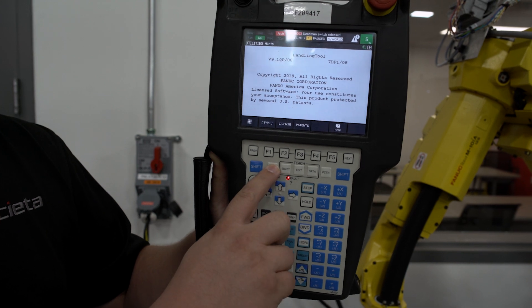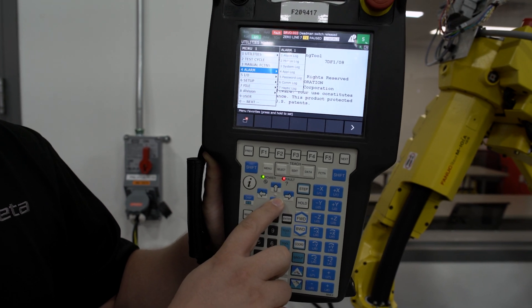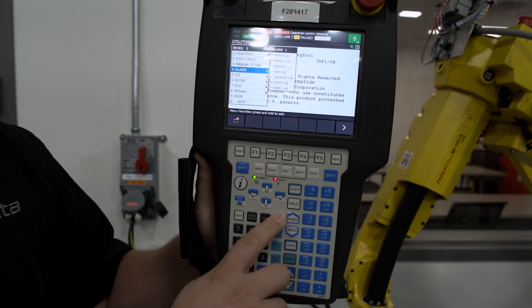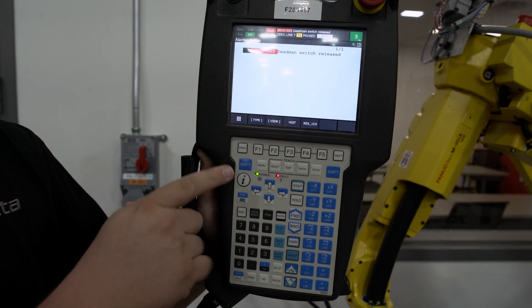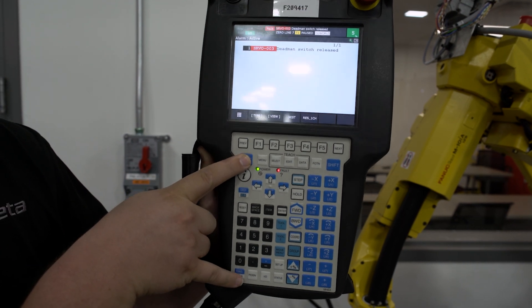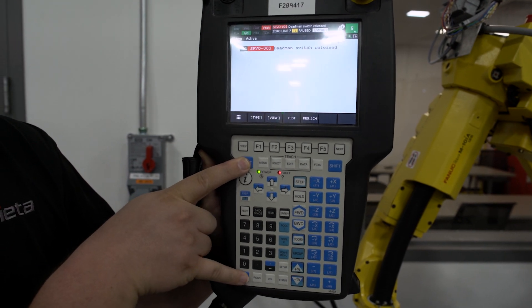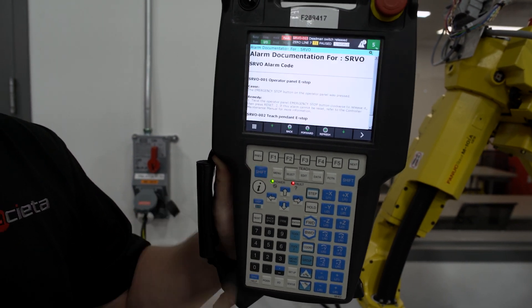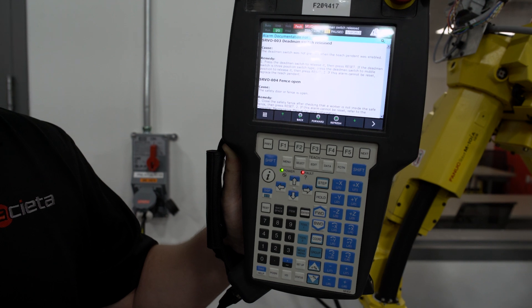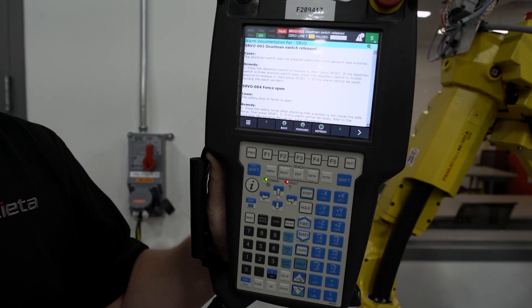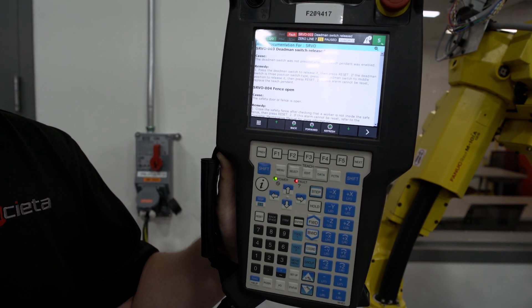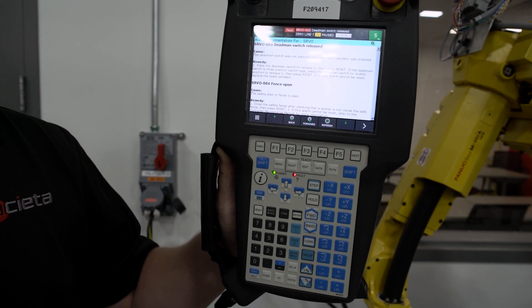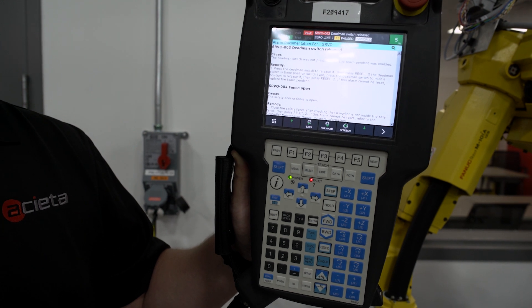By pressing our menu button, going to the active alarm screen, holding down the shift button, and then pressing our diagnose button at the bottom, this will open up the alarm documentation for the specific alarm that you are experiencing. This will give you the cause and other potential remedies.